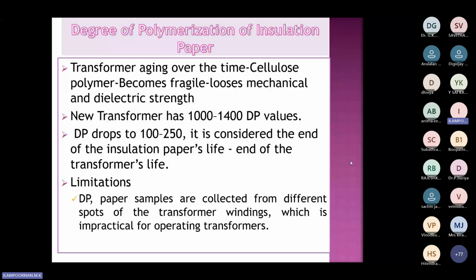Actually, the notebook is a perfect example to understand our transformer paper. What happens is first the moisture gets absorbed, and the degree of polymerization reduces. Then finally, if the degree of polymerization drops to 100 or 250, it will become brittle, meaning it turns into dust and mixes with the oil, becoming another form of dust in the oil.